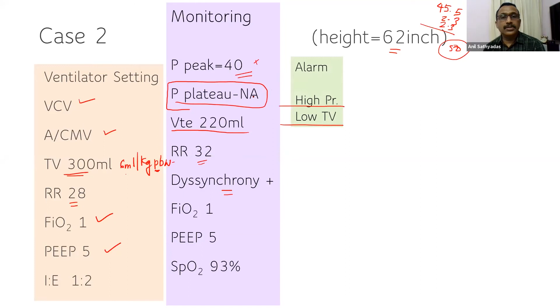That we understand because it is less than 250 ml, the alarm has come up. And high pressure because the peak pressure has already reached 40. So what are the differentials of low exhale tidal volume? Whenever I talk about tidal volume, that is the exhale tidal volume. As I've already said, it is a leak in the circuit.